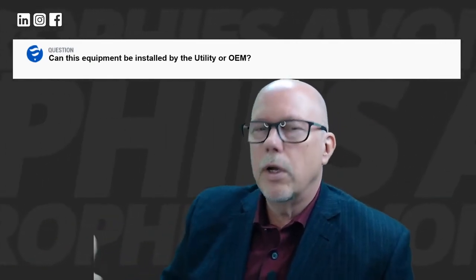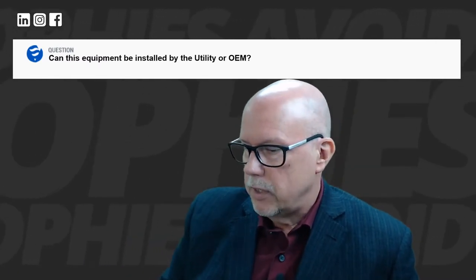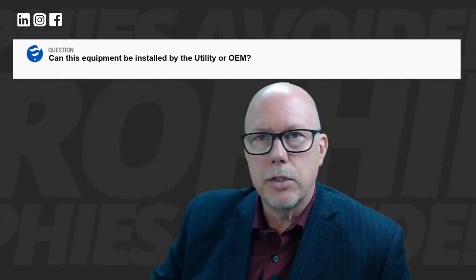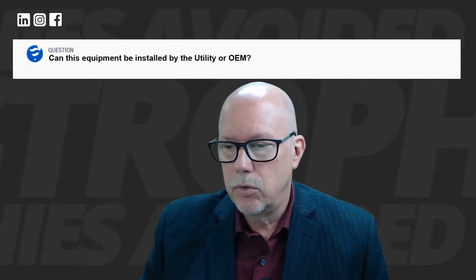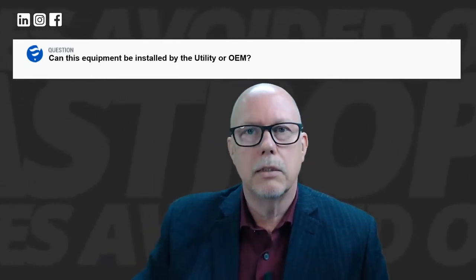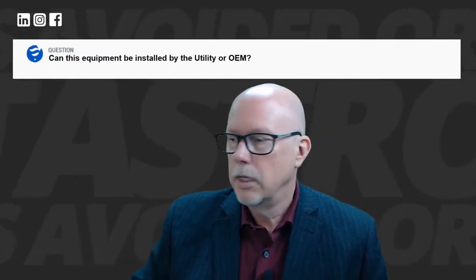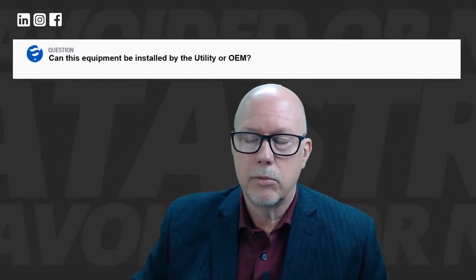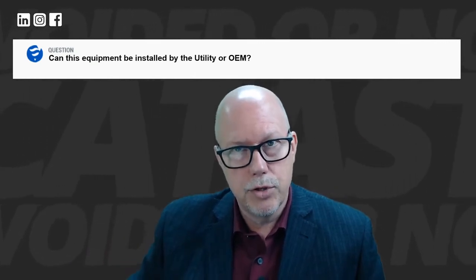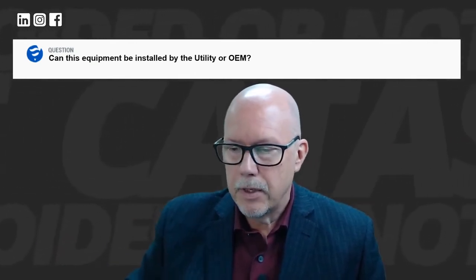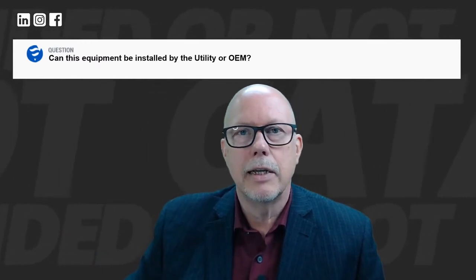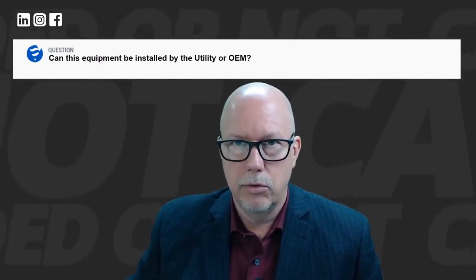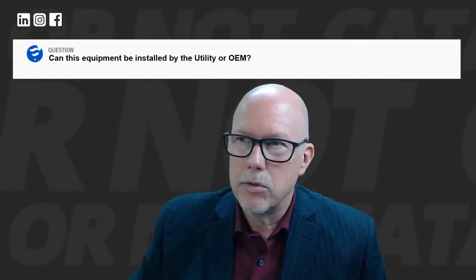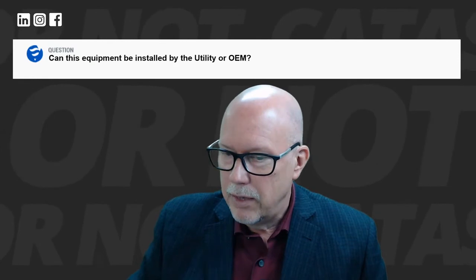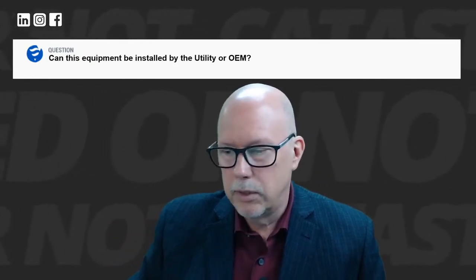So, to be serious for a second, here's what we always recommend. Let's say you have a power station with 4 units and you want to install the system yourselves. Please ask our service department to at least do the first one, or if possible, let them do all 4. That way, you'll be sure it's installed correctly. But if you want to do it yourselves, at least let our team show you how to do it, where to install, and what the do's and don'ts are. We're running cables through 18 kV, so you have to know what you're doing if you don't want to kill anyone, especially in a very harsh environment.